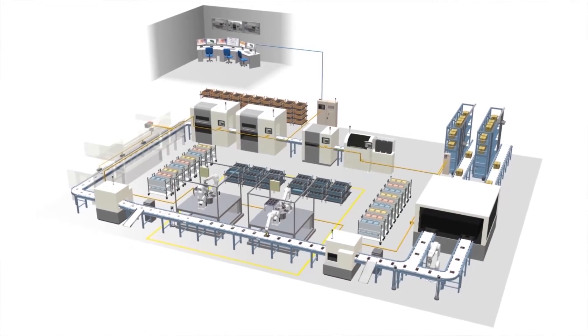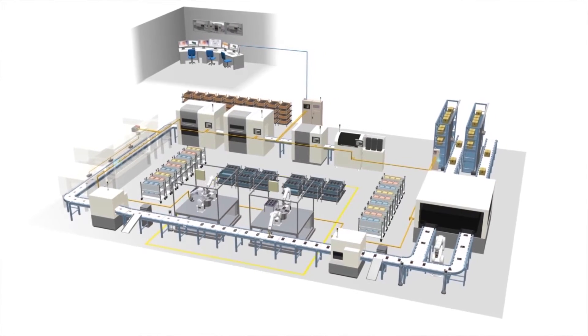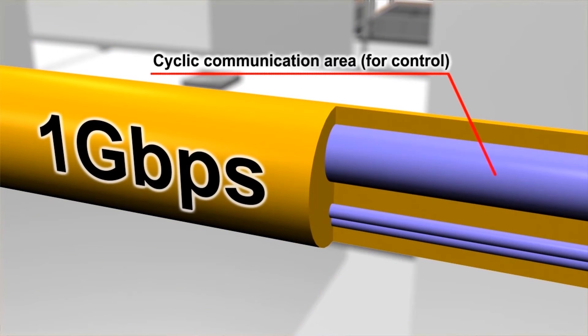The controller has an area of memory which is shared with all the devices on the network. To communicate with a given device, you simply change the data in the area of memory which corresponds to that device. The network automatically updates the data across the network without any need for programming.